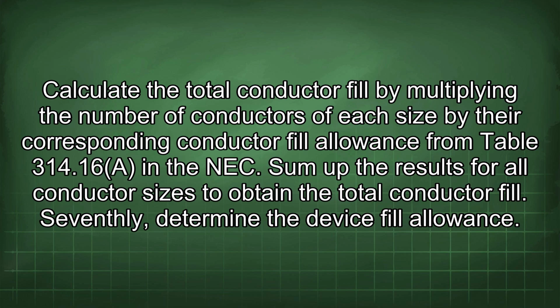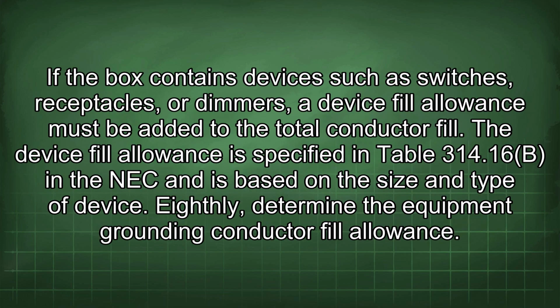Seventhly, determine the device fill allowance. If the box contains devices such as switches, receptacles, or dimmers, a device fill allowance must be added to the total conductor fill. The device fill allowance is specified in Table 314.16(B) in the NEC and is based on the size and type of device.